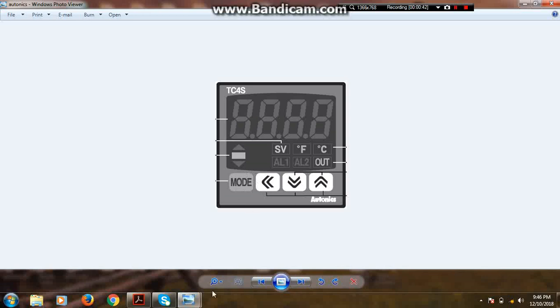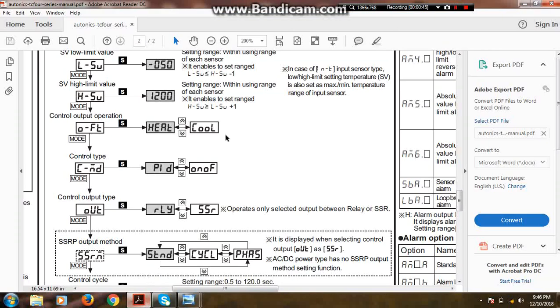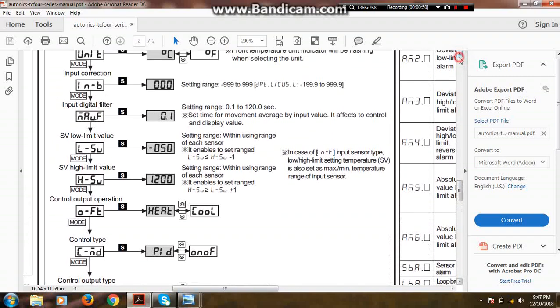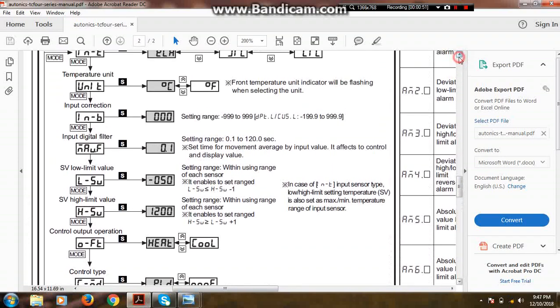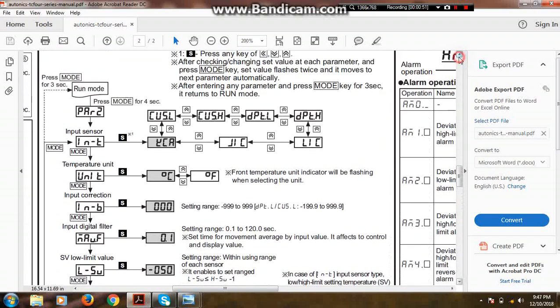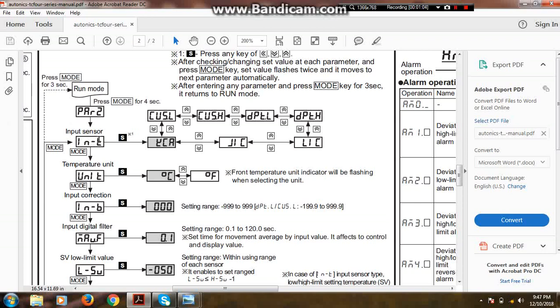Then you will see on seven segment display like this: PAR-2. In second group setting, the first important parameter is input sensor. There are two types of temperature sensors: thermocouple and PT100. If we want to select the thermocouple for temperature measurement, then we select in input sensor KCA. If we use the PT100 for temperature measurement, then we will select DPEL.